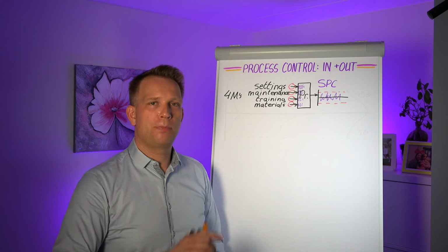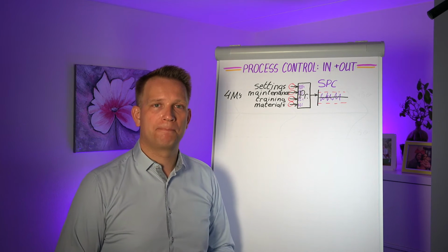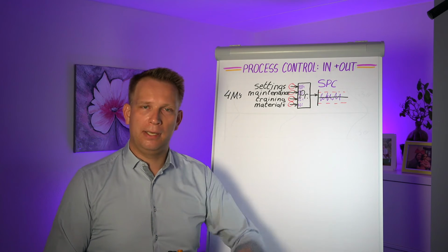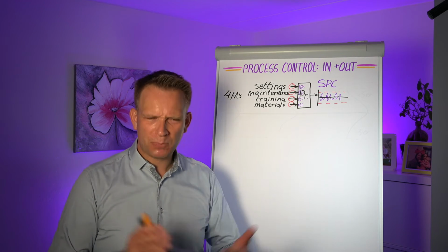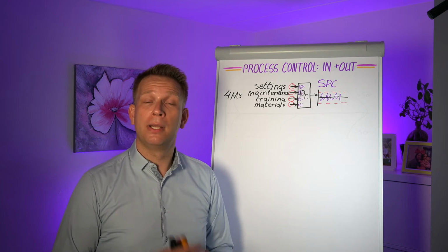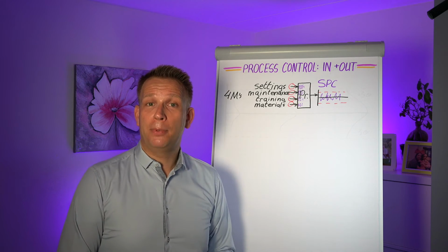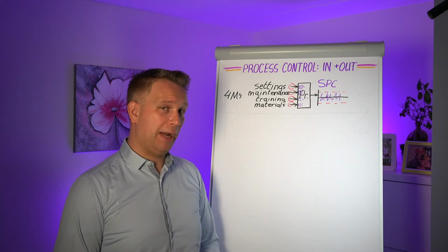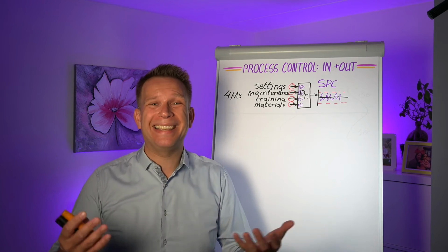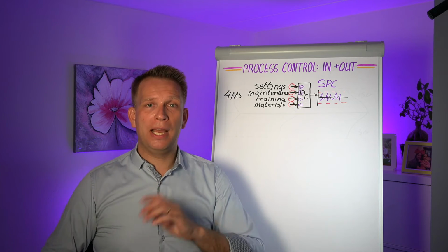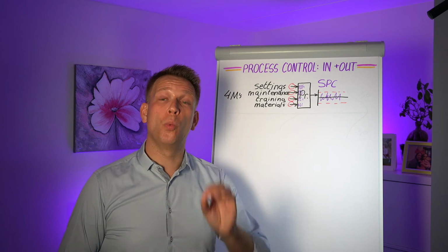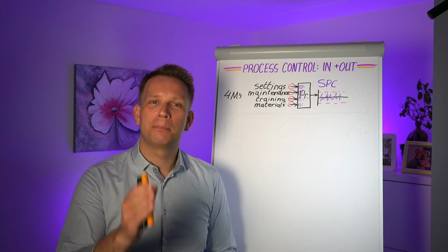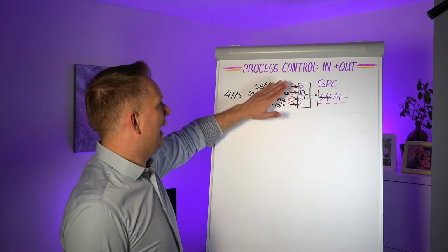If you say the process should be set at 190 degrees Celsius, and then an auditor comes in, they check the system, it's at 192, you get a minor. You get a remark, you might lose your certification, and that is something the quality department wants to prevent at all costs. So what they say is, it should be set somewhere around 190. But that's not a standard, right? Now, you want to have a set point and a specific instruction when you're allowed to deviate. Don't please some external auditor, please your own processes. And that requires set points.